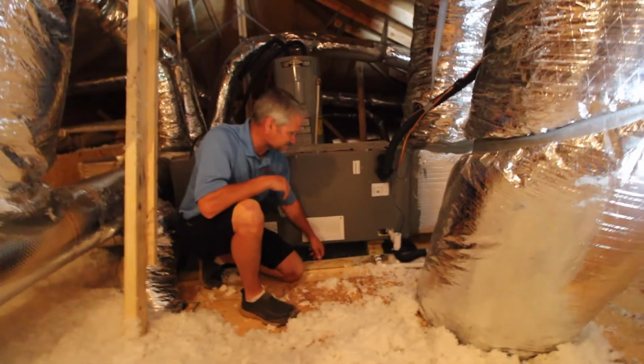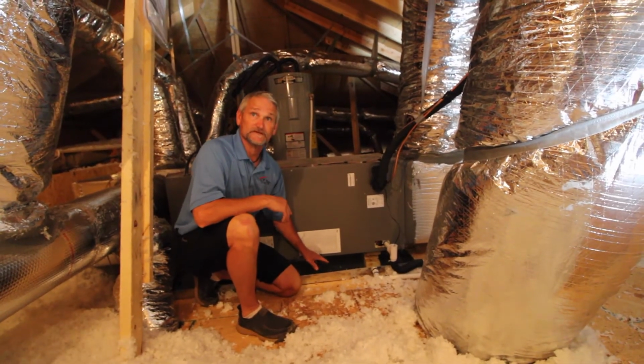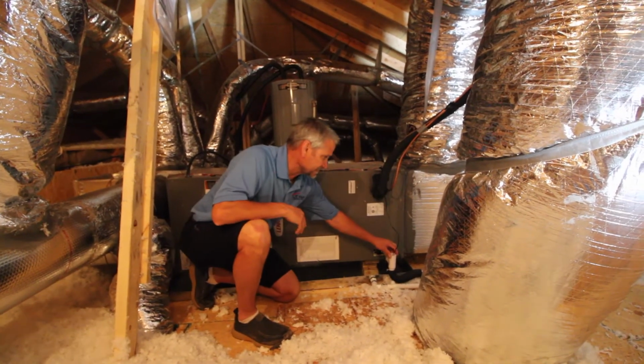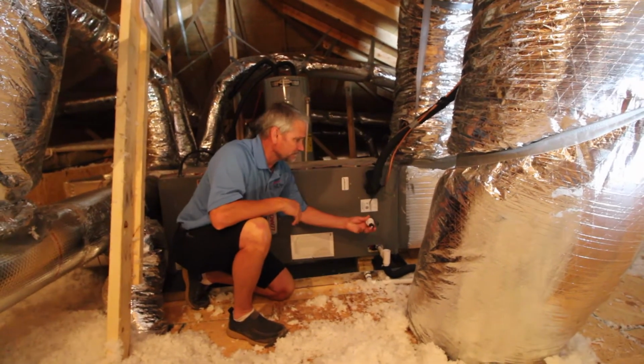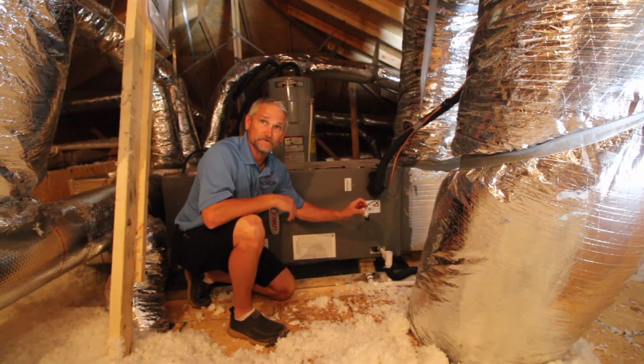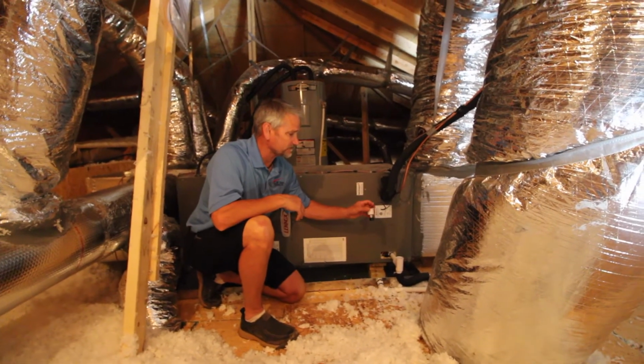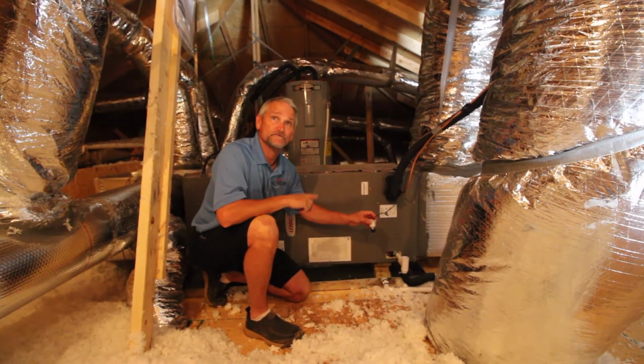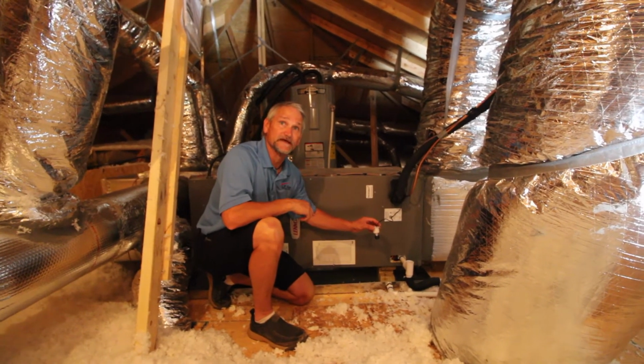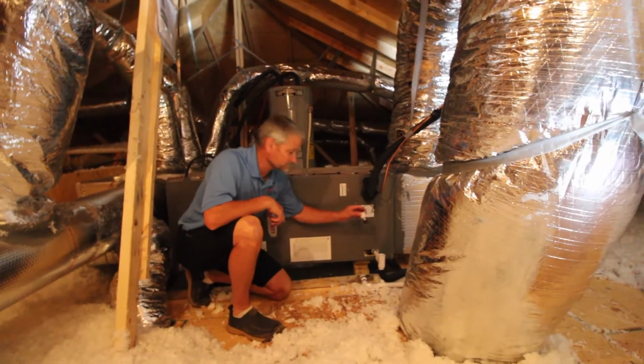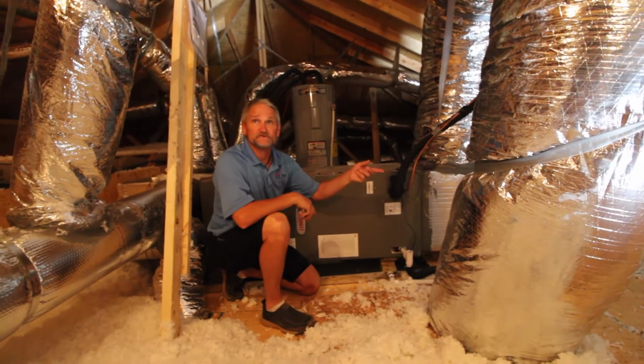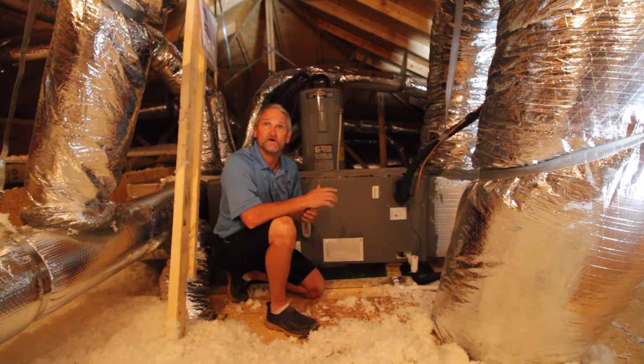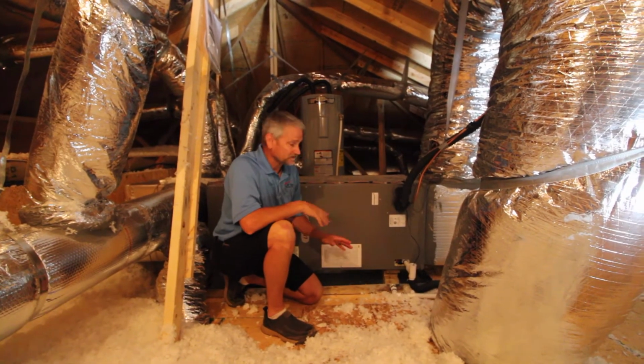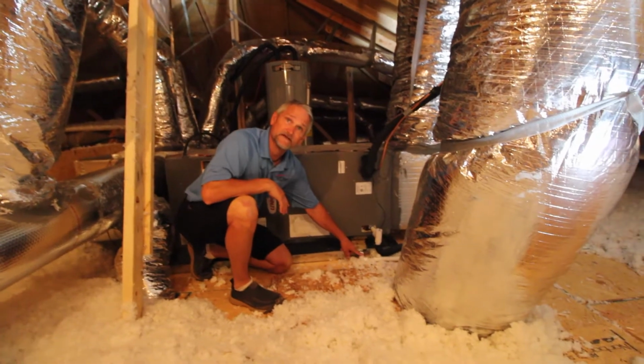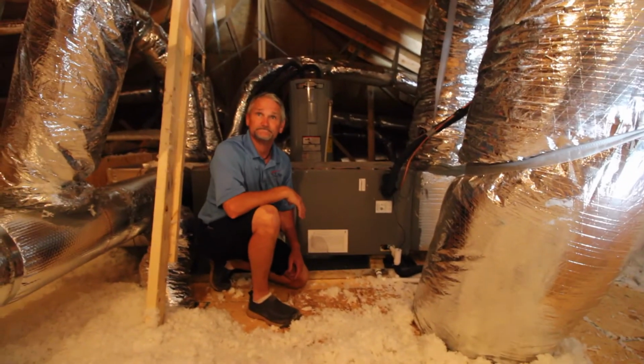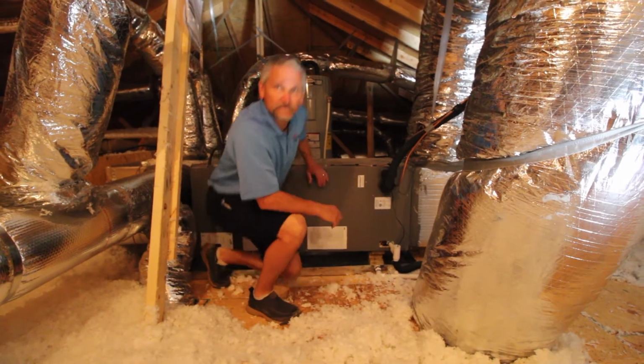First, your unit sits in a pan, so hopefully if there's ever a backup, the pan will catch it. Second, if there's a clog in the drain line, there's a float in the drain line that will shut your unit off. When it shuts the unit off, it goes straight to the thermostat, and your thermostat will be blank. So if you ever get a blank thermostat, come check to see if you have water in your pan. If there is water in your pan, use a shop vac on the outside of the house to suck out whatever clogged it, and the problem should go away. The second drain line is strictly for the pan itself, and hopefully we'll never have water in the pan. You do have a float switch.